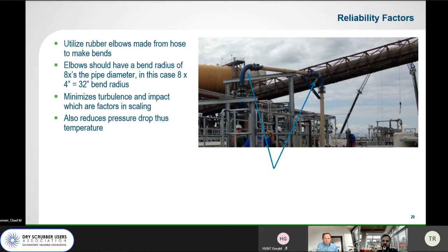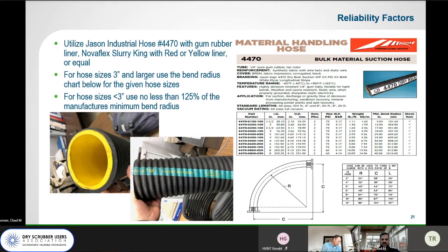Elbows in the system. We like to use long radius elbows made from rubber hose. These are a system design that used a cast iron wear elbow because this vendor thought that hydrated lime was abrasive like ash and would eat through elbows, and that's just simply not the case. And also made it very challenging to change these elbows out in certain areas due to their weight. So a standard that we use on our new systems is a urethane kind of gum rubber lined hose, it's an abrasion resistant liner. I've had these hoses in service since 2015 with no wear through. And again, 8 times the diameter is typically the hose radius that we like to use to minimize turbulence and mixing in those areas to try and maintain smooth and even flow.